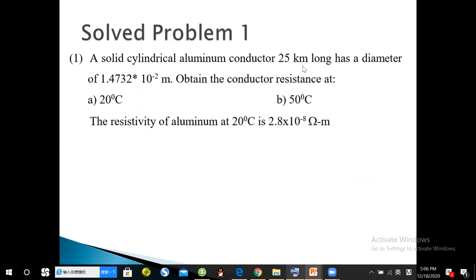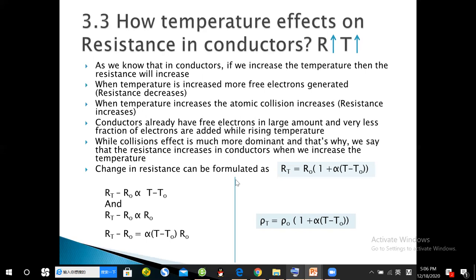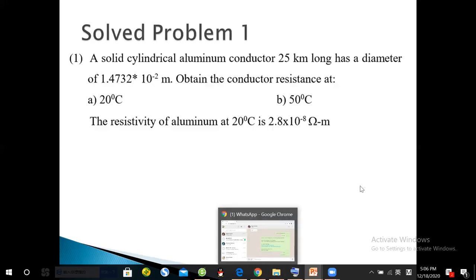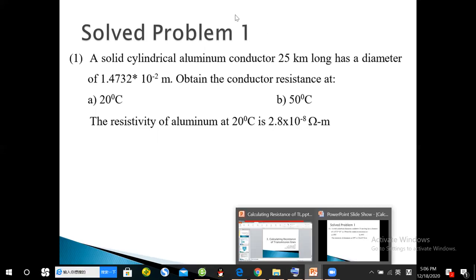Problem one on the sheet: a solid cylindrical aluminum conductor 25 km long has a diameter of 1.4×10⁻² m. Find the conductor resistance at 20 degrees centigrade and at 50 degrees centigrade. The resistivity is given. Note that alpha for aluminum — the temperature coefficient — is missing from the problem; it should be looked up, approximately 0.00429 per degree centigrade.